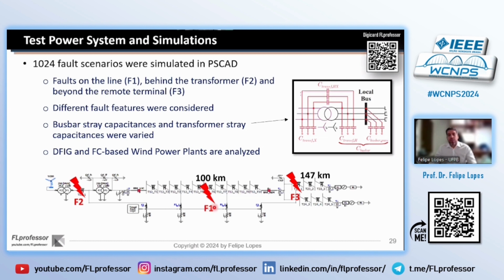The point F1 is related to an internal fault, F2 and F3 are external faults on the IBR side and on the grid side. Different fault features we're considering, and we varied the stray capacitances considering different IBRs like doubly fed induction generator and full converter wind power plants.